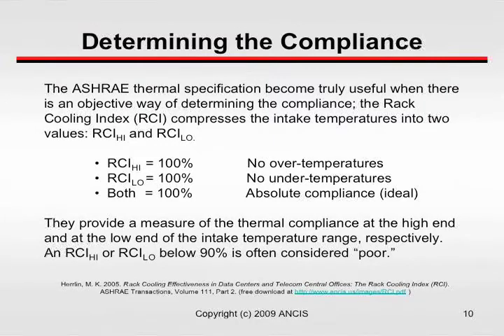Determining compliance, and this is important because now we have the recommended range and allowable ranges for temperature. How can an end user or a consultant demonstrate that this particular design will operate within the recommended and allowable ranges? Well, then there is this nifty thing called the rack cooling index. We have two parts of it, RCI high and RCI low, and as it sounds like, high is the high range and low is the low range.